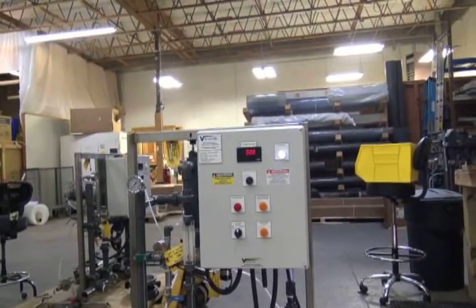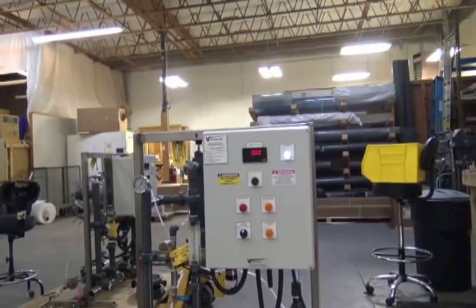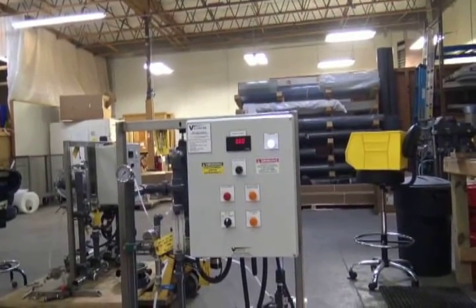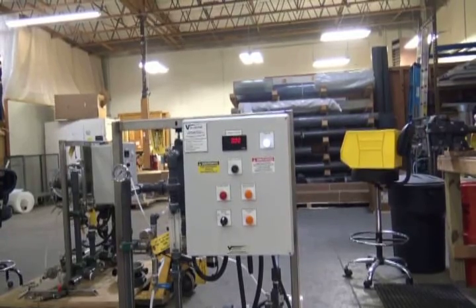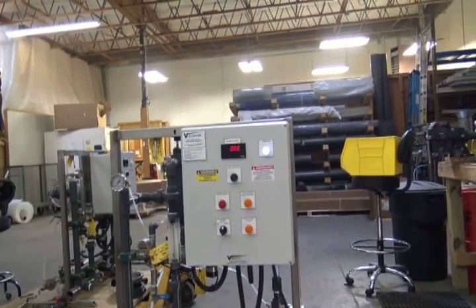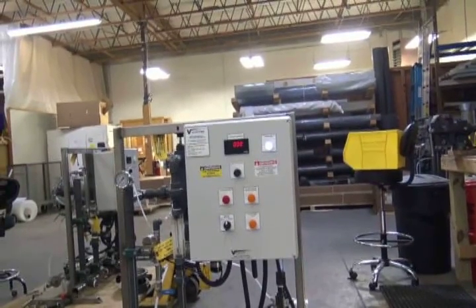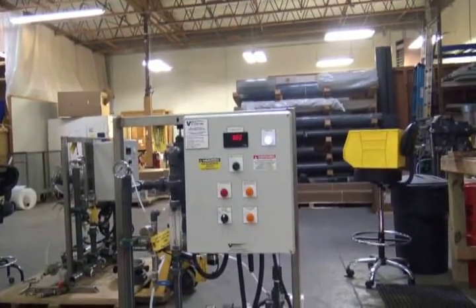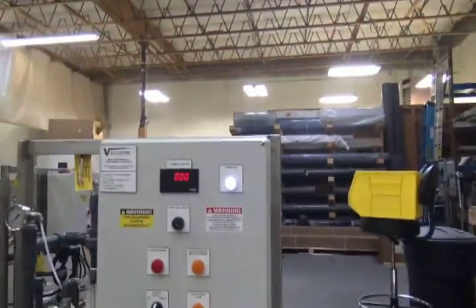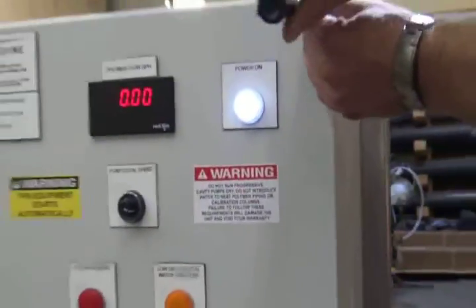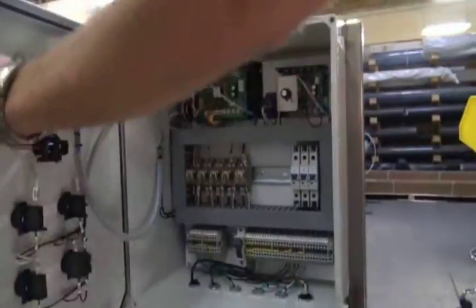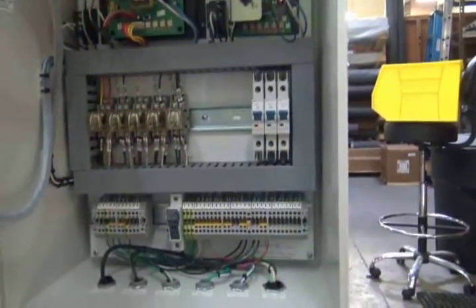This video is on how to calibrate a thermal flow sensor on a D level and up system, not including PLC controlled panels. So first, what we would do is open up the panel and disconnect the signal wire. How to do that is there's a terminal block that has a disconnect blade. Just slip that open, pull it out, just like so, and then we're done.